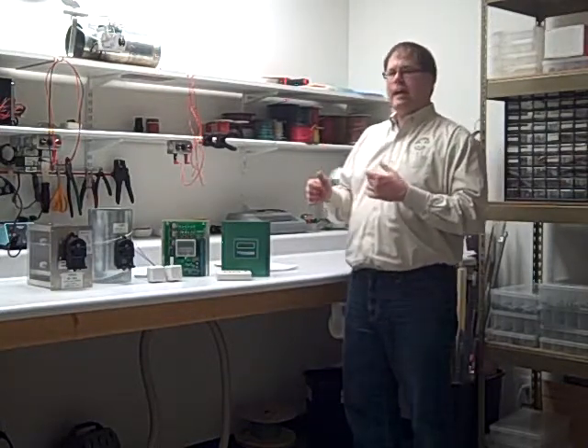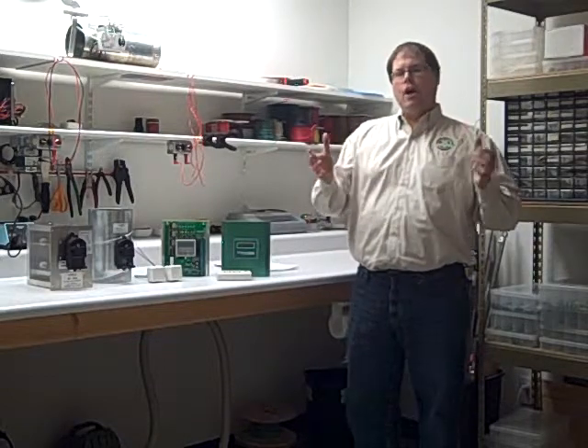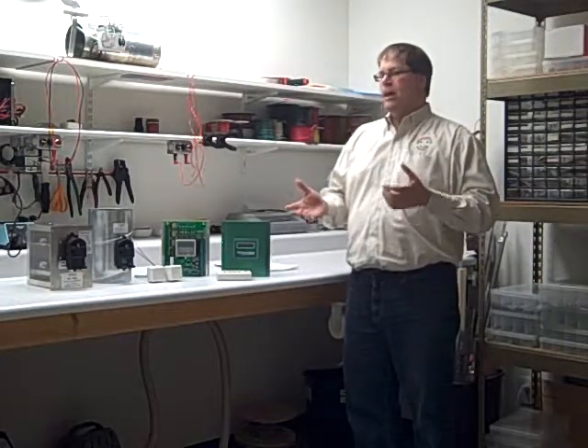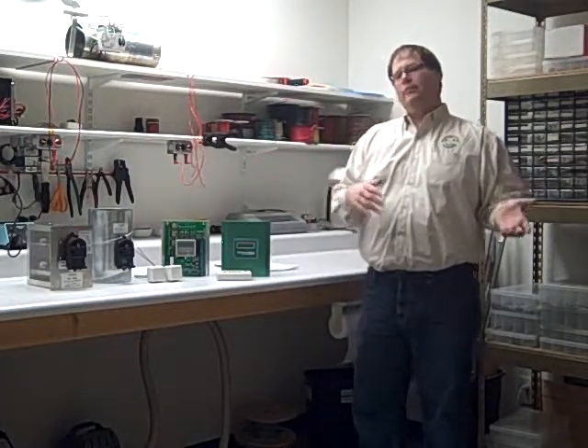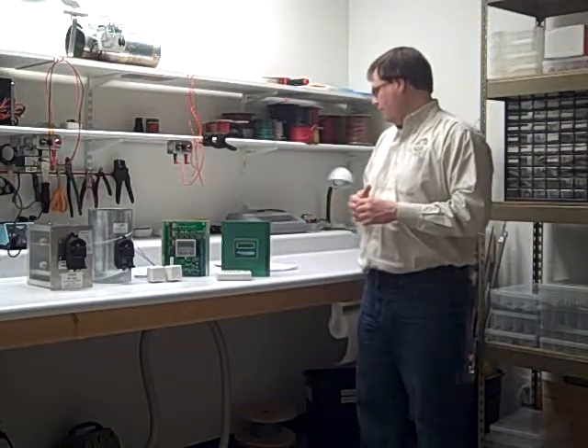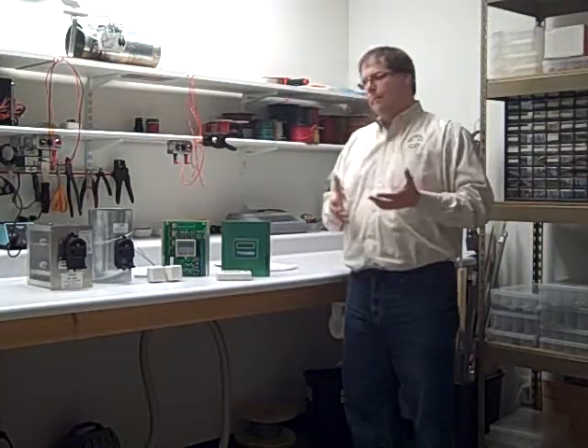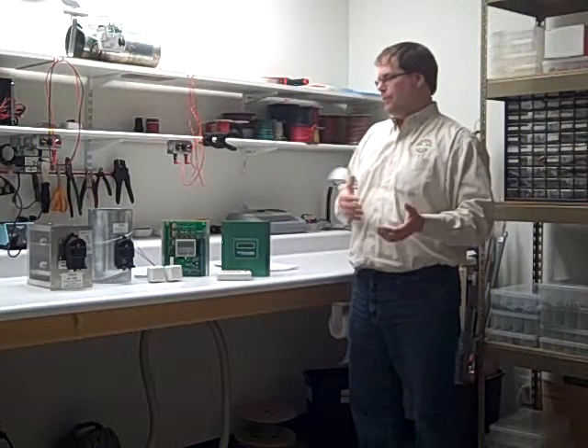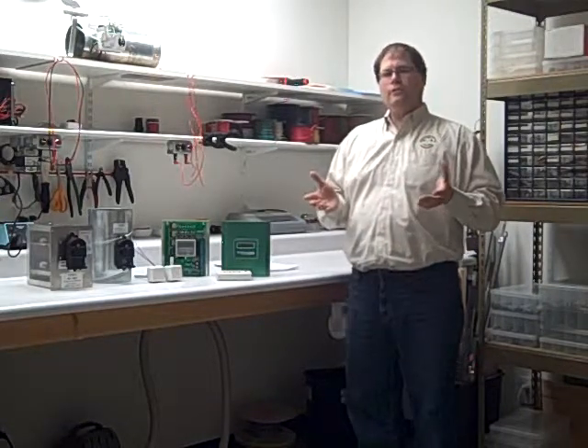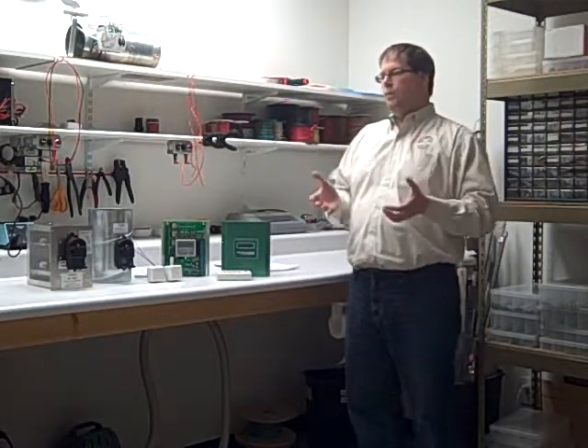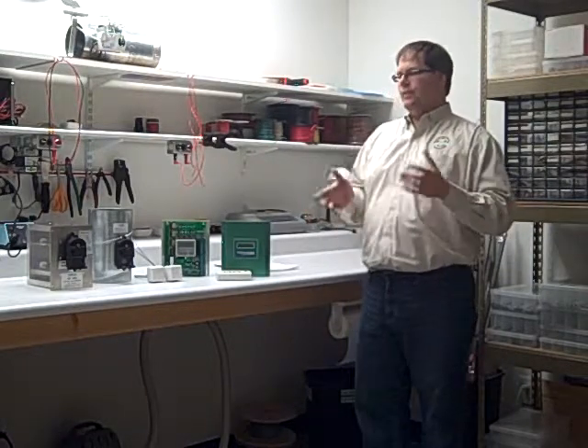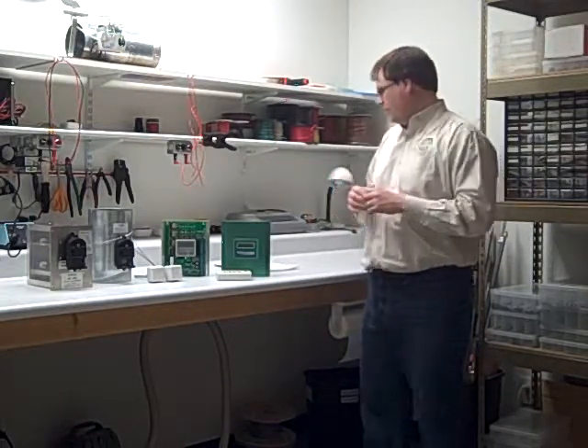So you go up to the thermostat, and when there are no calls and you want to be in the ventilation mode, you can control which zones actually get ventilation and which don't, just by simply controlling it through the thermostat. There's a purge cycle if you want to have control over the purge cycle. In other words, after all zones are satisfied, what do we do? Do we dump that air into the last zone calling, or do we spread it out across all zones?